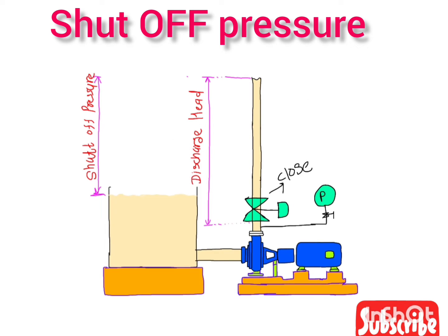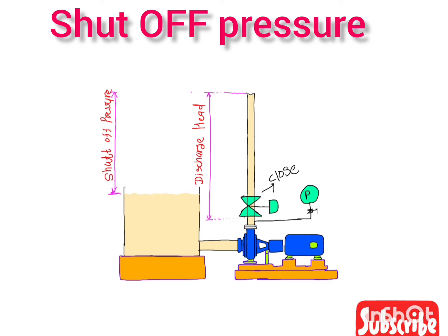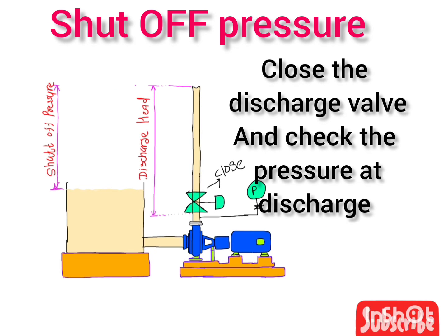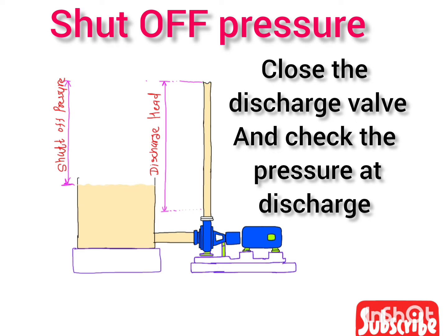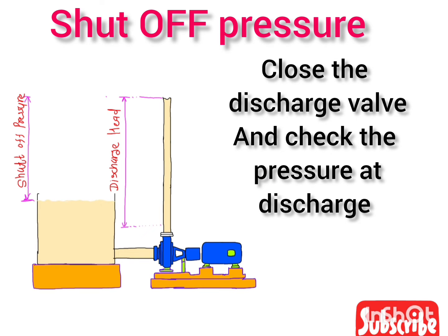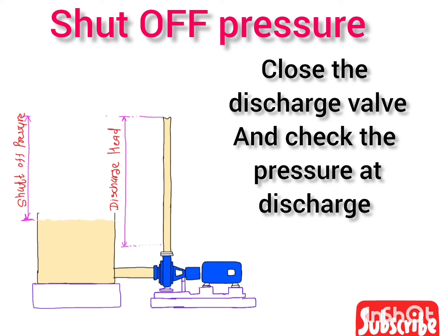If you want to know the shut-off pressure of your centrifugal pump, simply close the outlet discharge valve and observe the maximum pressure that the pump generates on the discharge side. That maximum pressure is your shut-off pressure.